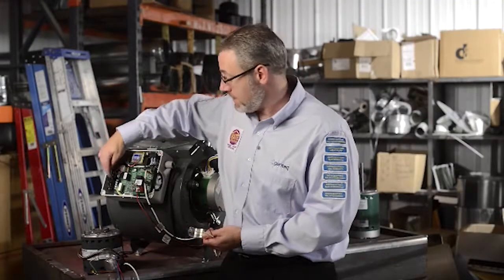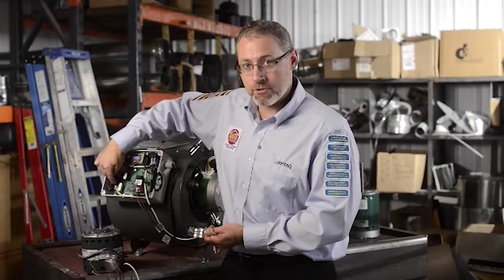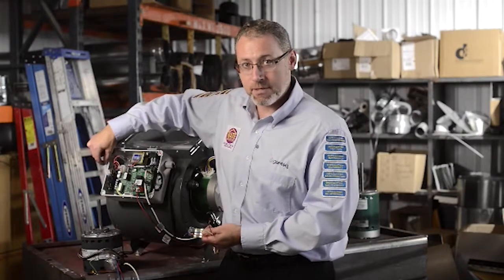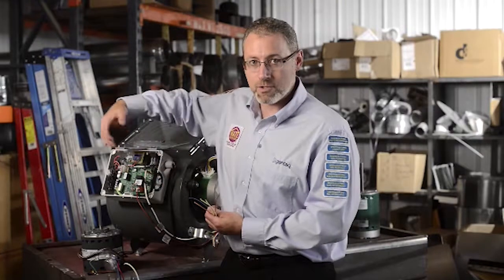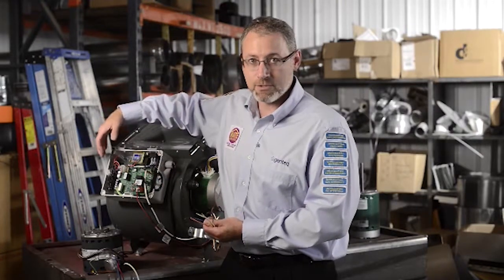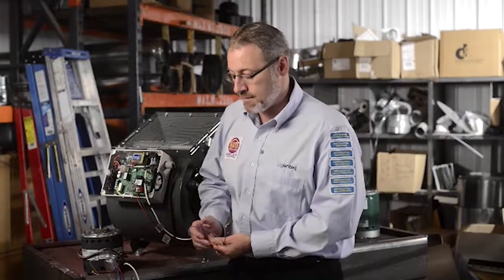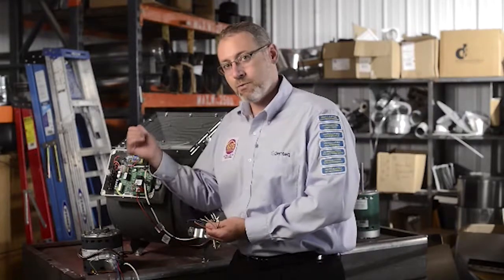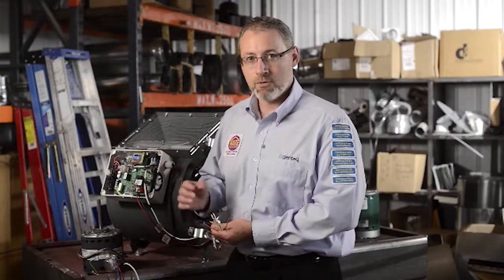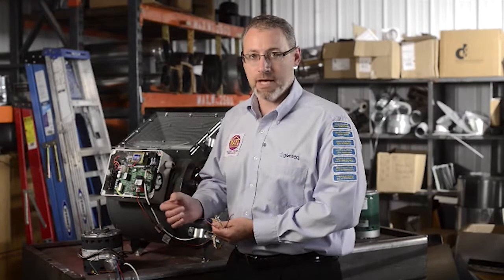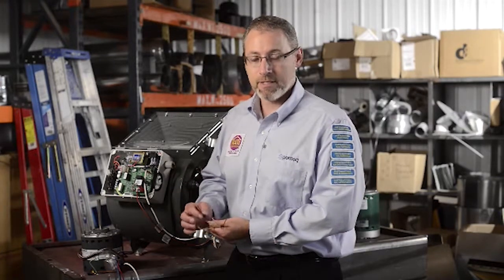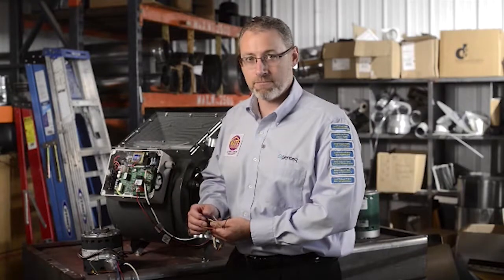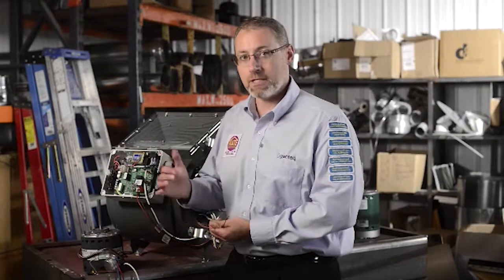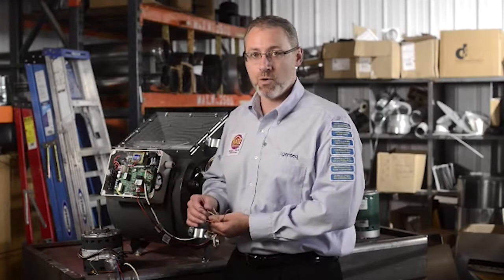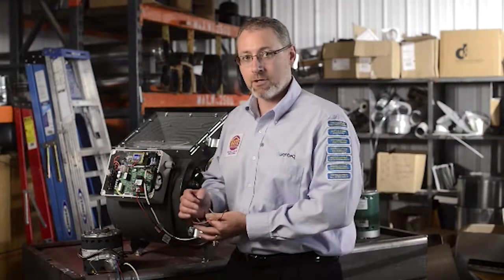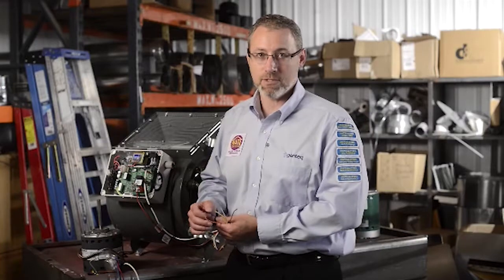and I actually recommend, from the installations that I have done in my own home or for my family, that you leave the wires that are already under those terminals there, come back about 6 inches, and wire nut these wires into the wire that you want it to be connected to. Because it's going to be very common that the wires that we're using and the wires that are already under those terminals could be a different gauge and a different design. Our wires are stranded, and the wires that are under those terminals are quite often solid core. Mixing these wires under one terminal could cause one wire to be looser than the other and cause a future failure for the HVAC system.